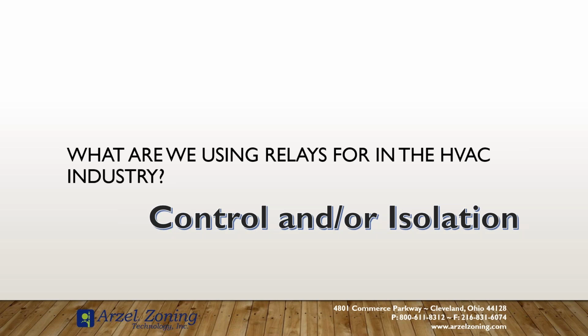On the isolation side of things, you have a humidifier or the Arzel panel. Perfect example. The Arzel panel has its own transformer. The transformer in the Arzel panel powers all your thermostats. However, your furnace has its own transformer as well. We cannot tie those two transformers together, so we have a bank of relays on the Arzel board that provide you your isolation. So your HVAC outputs on the Arzel panel are dry contacts. We'll talk about that a little bit later, but that is your isolation.